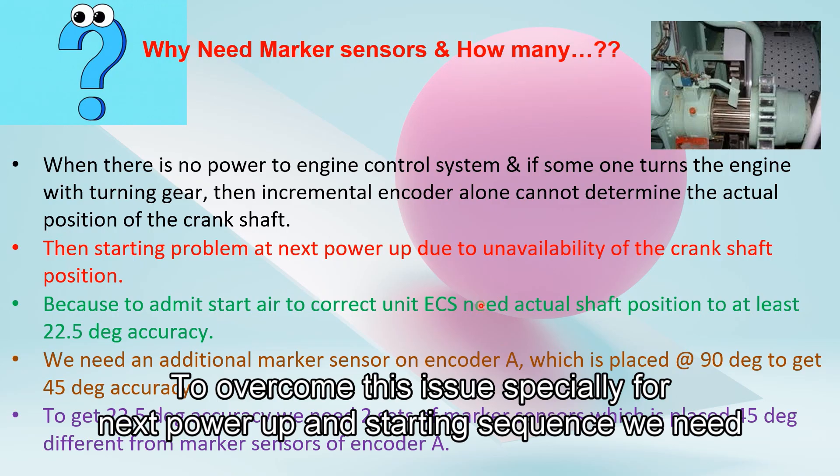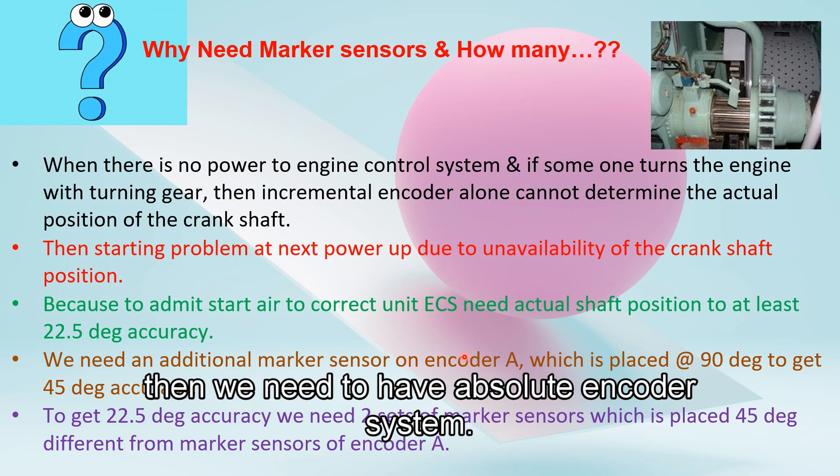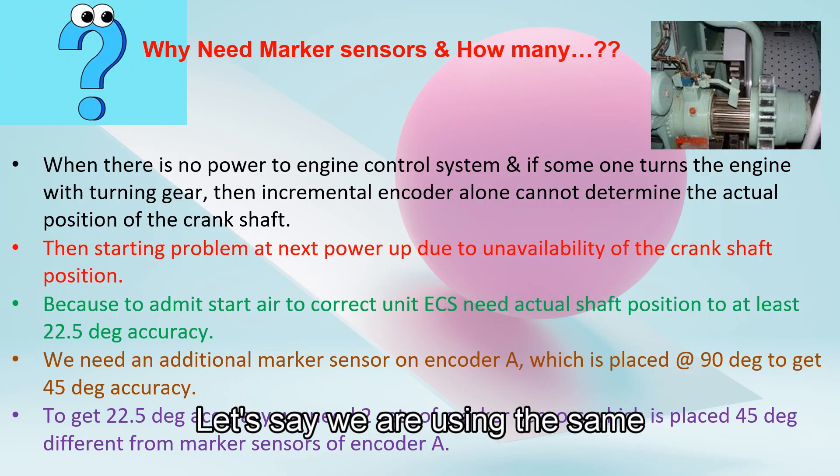To overcome this issue, especially for the next power-up and starting sequence, we need an accuracy of angle up to 22.5 degrees to admit the starting air. So to get the engine position accuracy to 22.5 degrees, we need to have an absolute encoder system.